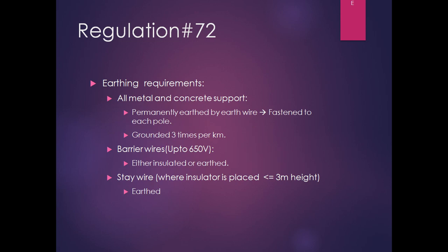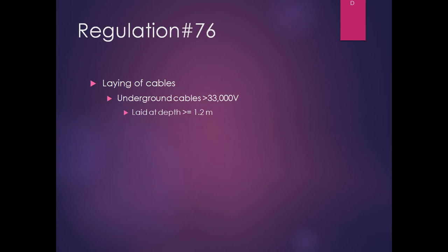Regulation 72 covers earthing requirements. All metal and concrete supports shall be permanently earthed by earth wire fastened to each pole so that each pole is in contact with earth. The earth wire shall be grounded at least three times per kilometer and, as far as possible, at equidistant locations. Barrier wires up to 650 volt shall be either insulated or earthed. Stay wires where the insulator is placed less than 3 meter in height shall also be earthed. Underground cables of system voltage exceeding 33 kV shall be laid at a depth not less than 1.2 meter.